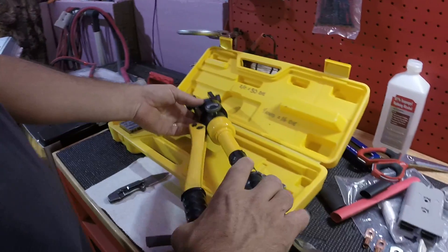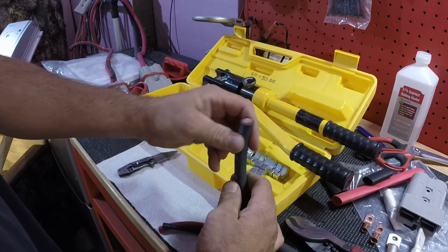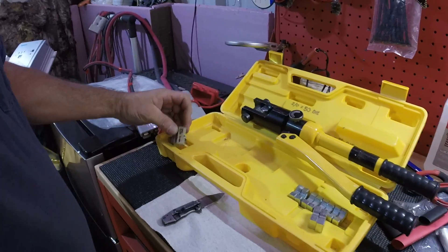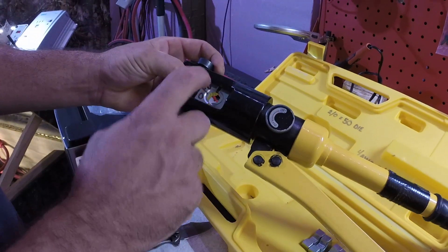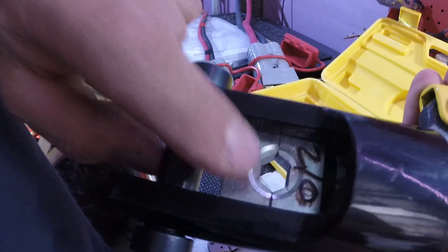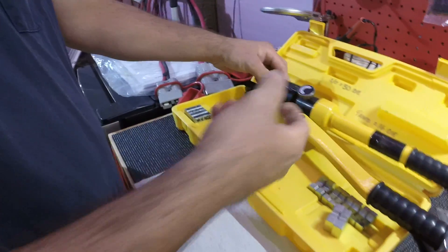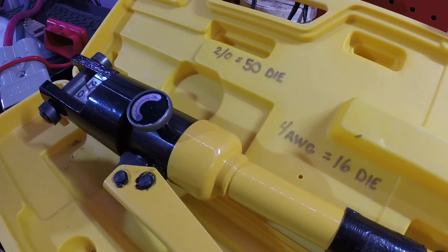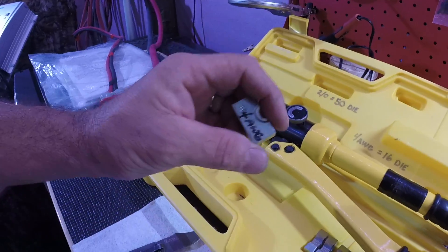I'm going to be crimping some 2-0. Today I'm upgrading some of my cables. When you get a crimper like this, you're going to have to figure out what size die is for what. When you figure it out, make sure you mark your dies. The one that does 2-0 is the number 50 die. Just write them down somewhere so you'll remember. 4 AWG is like number 16.